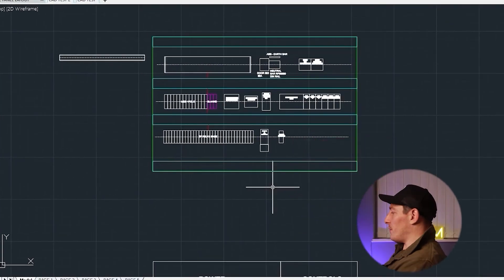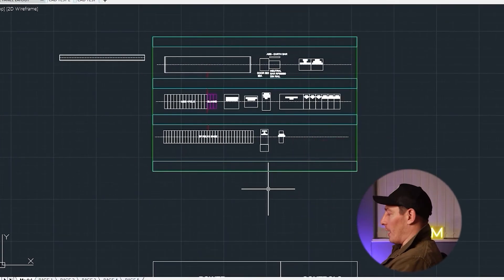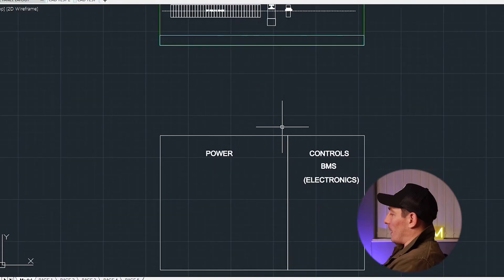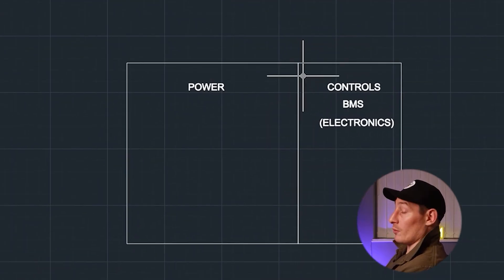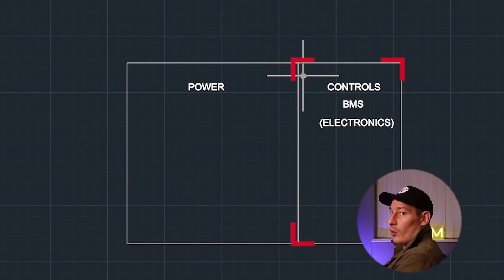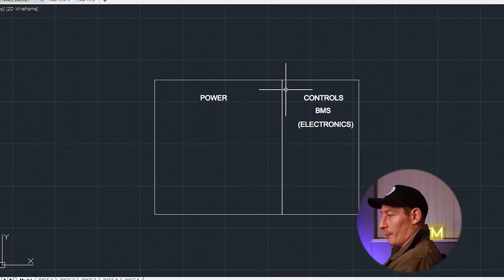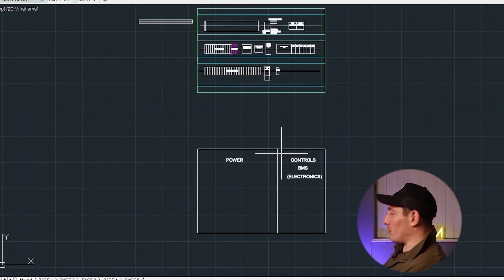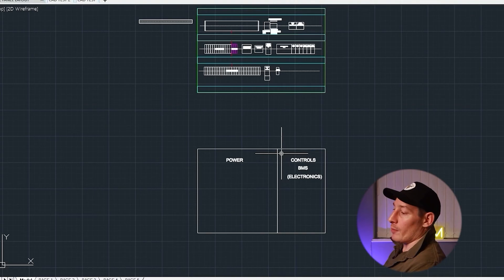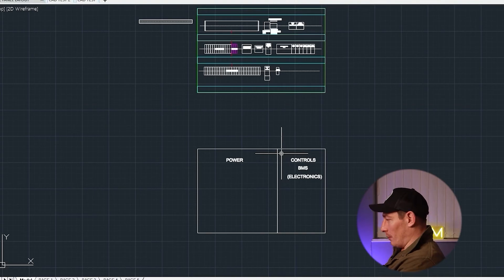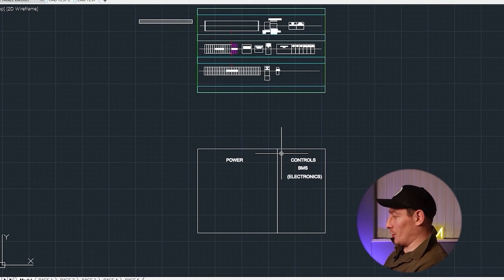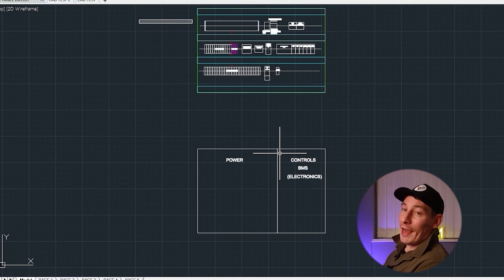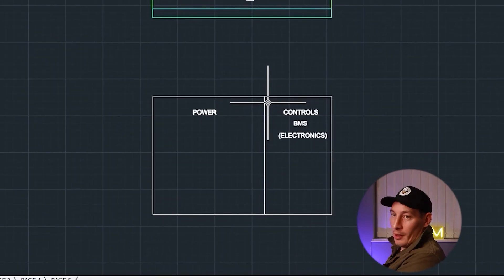What you'll tend to find on larger, higher-end panels, they tend to split the panel into two sections. So they have a panel for the power and then they have a panel for the controls or the BMS - ultimately what's holding the electronics like the PLC modules. Now on this panel I don't think it's necessary to do that, but when we move forward onto the next stage and I spend a little bit more time spacing everything out, making it look a lot nicer and neater and putting it into a logical order, it might be that I arrange it to match that power on the left and the controls on the right.